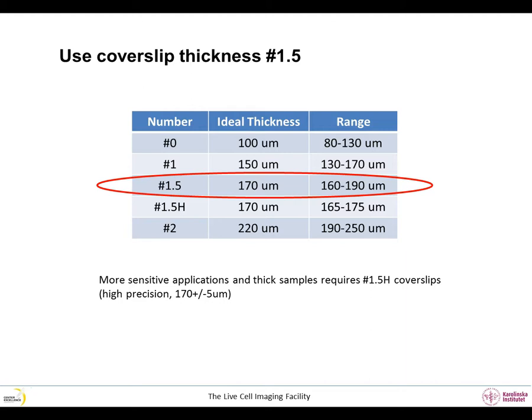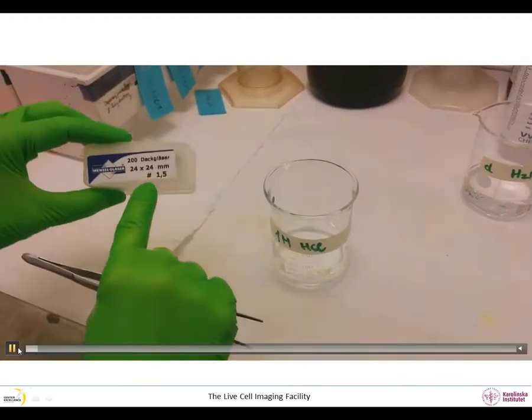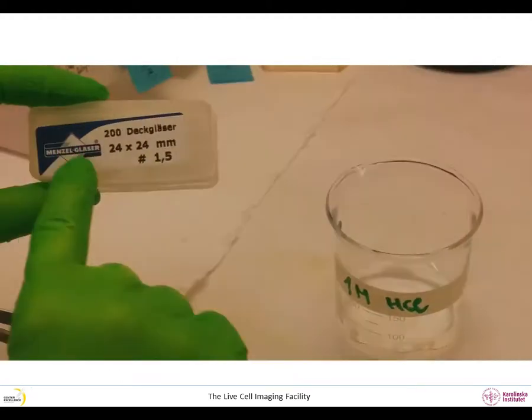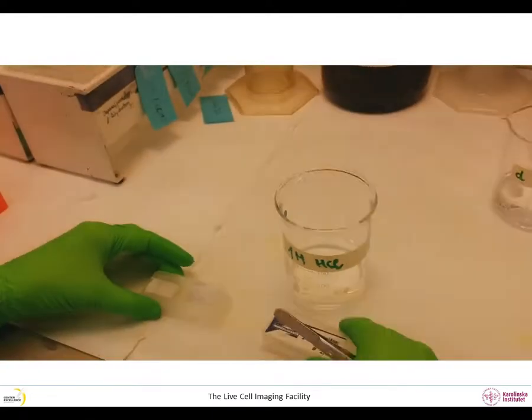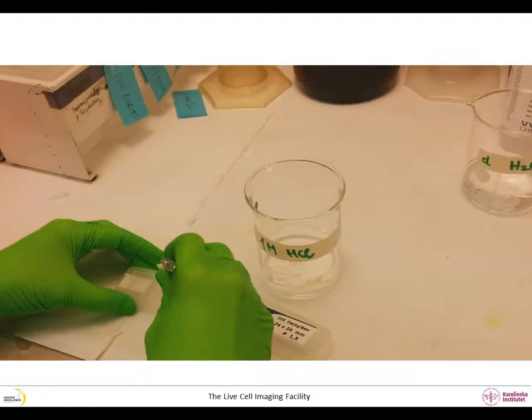Objectives are designed to be used with cover slips with a thickness of 170 micrometers and with the sample directly on the cover slip. Buy cover slips labeled as number 1.5. They have a thickness between 160 to 190 micrometers. Please pay attention so that you pick cover slips from a box having number 1.5 written on it. Using the wrong one may have serious implications for your imaging.